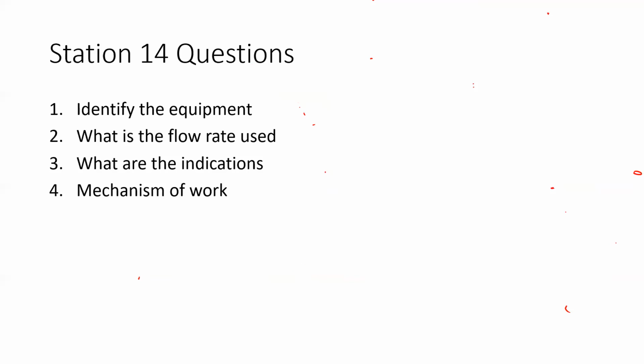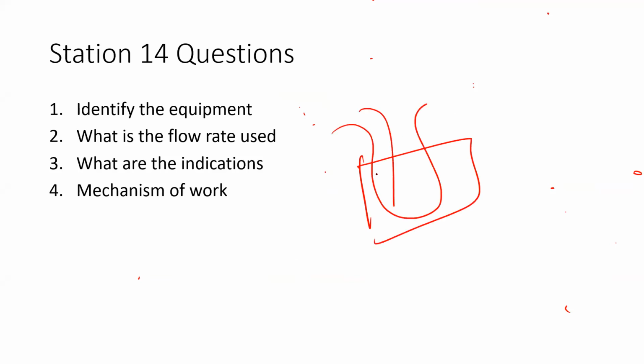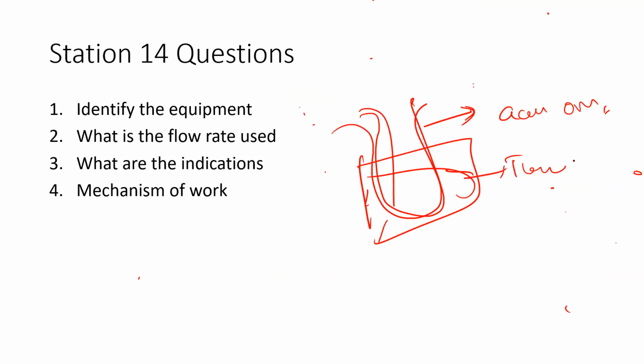I mean, actually, the circuit hasn't got any direct communication with the water. Say for example, if the water is heated, it just goes through the tube and it is heated externally to the water. The gases going inside the tube, so there is no chance of leaking into the tube. But the problem is, when you overheat it, there is a chance of accidental overwarming of the gas. So that can produce burns in the patient's nasal mucosa. In order to avoid that, we have a temperature sensor which cuts down the temperature when the set limit is reached.